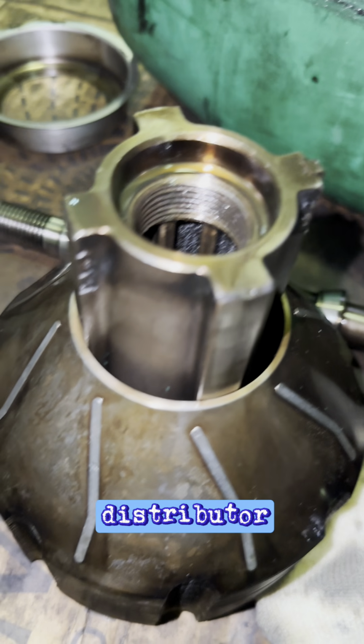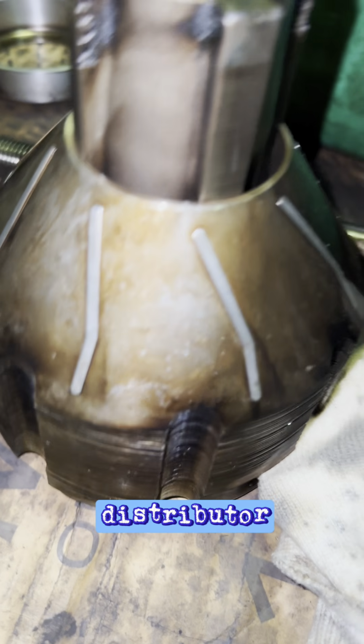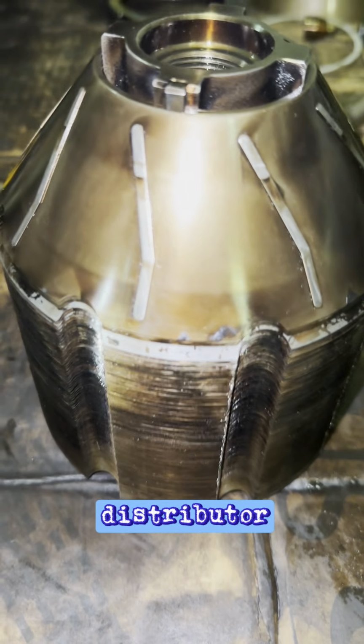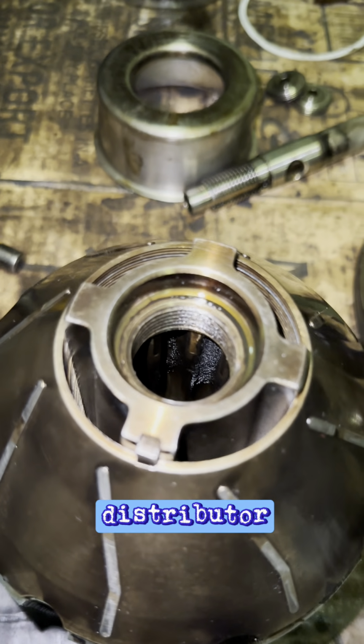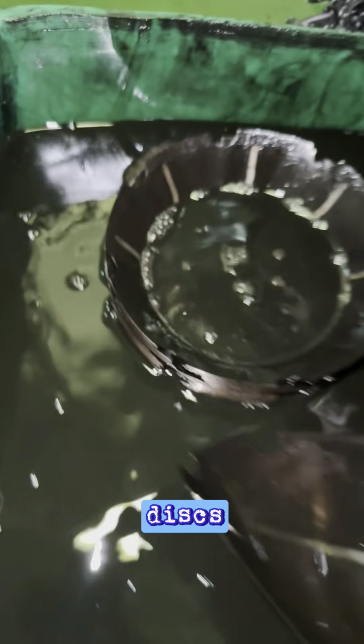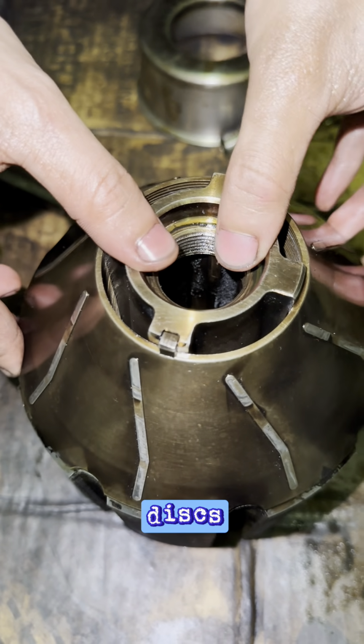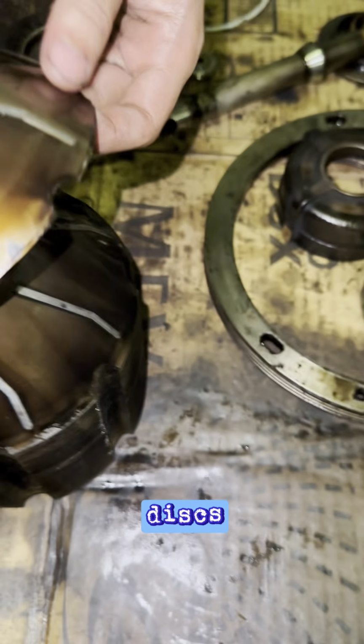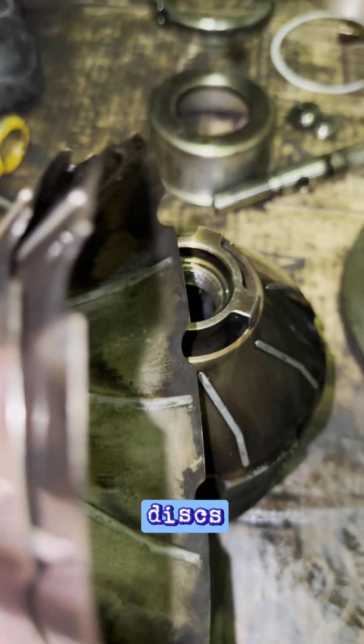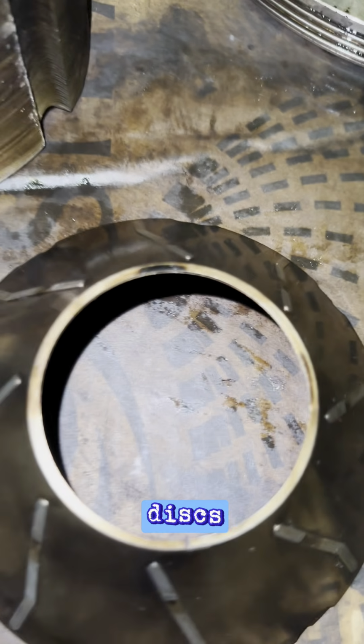Distributor, used to hold discs in place and directs the flows of dirty liquid to the bottom, then to the discs as the oil flows upward. Discs divide a space within the bowl into small passages in order to break the bulk of oil into smaller quantities, which is confined to pass through small passages provided by the arrangement of discs.